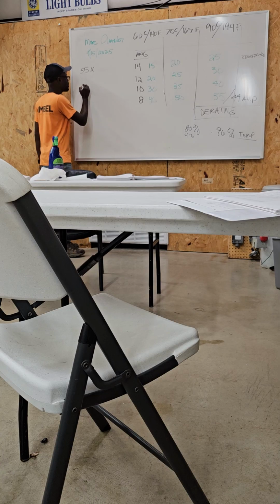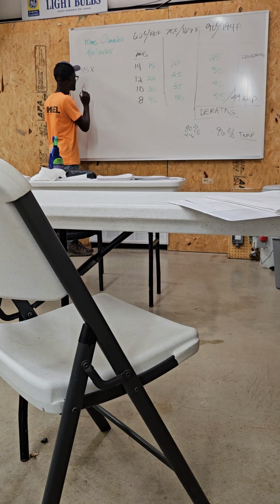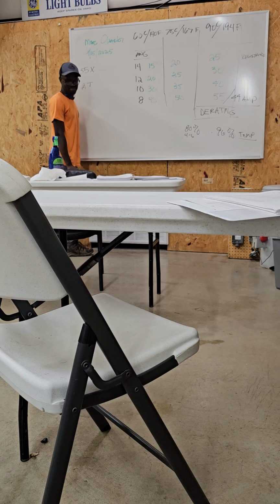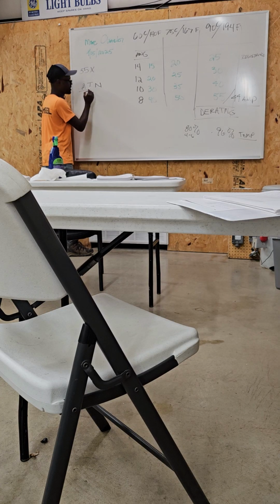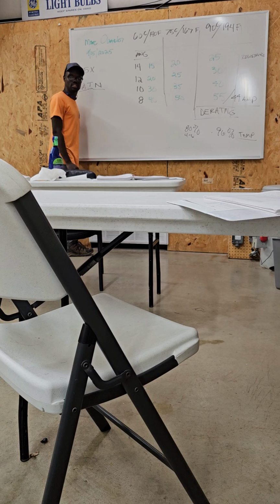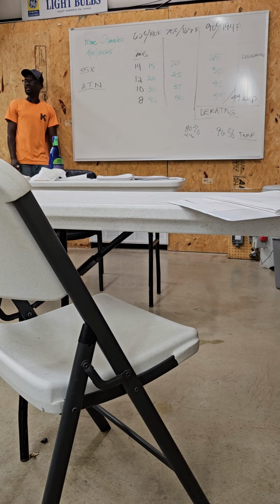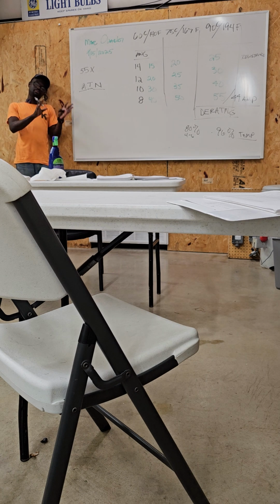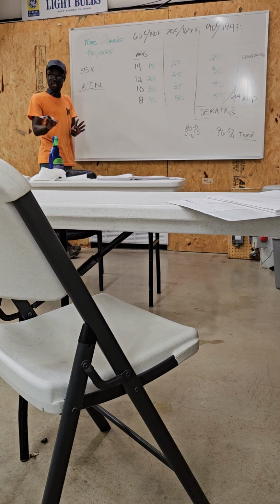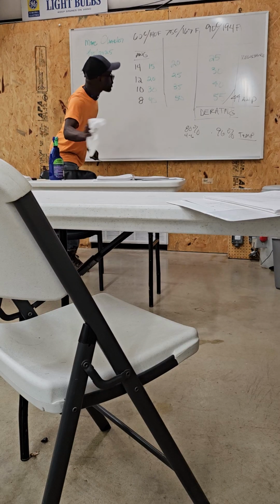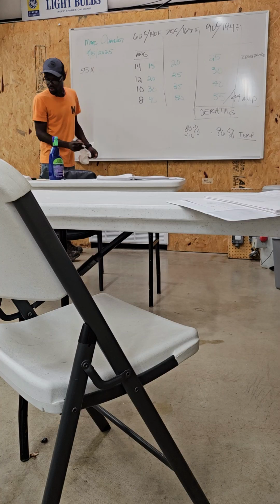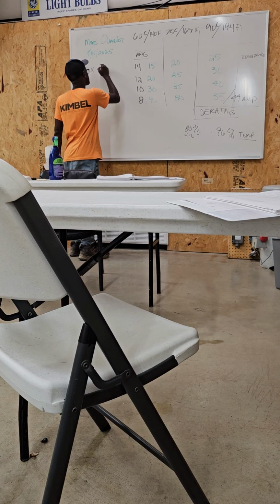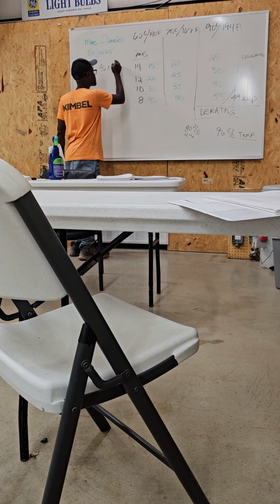The best way to remember it, I made that rule: it's A, T, N, not ATM. Amp, temperature, number of conductors. If you remember that, you will always remember how to do the formula. You'll be like, which one do I do first? Do I do the temperature first, or the percentage? So you always go with your amperage, then the temperature. What was the temperature? 0.96, right? Times that by 0.96. Times that by 0.80.